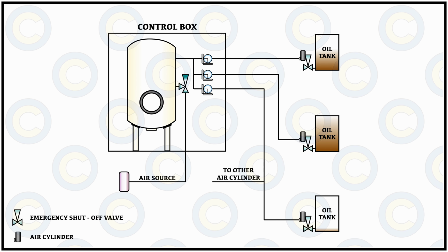Now, what it would mean is that first of all, there would be a main valve from the tank which should always be in an open position to ensure that in case of emergency, when you are operating it from the remote location, that is the location where this entire mechanism is situated, you just have to operate the valve of the particular branch or the particular zone that you need to trigger. And then moving on to that particular zone.